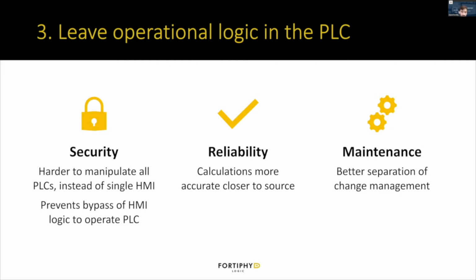For reliability, this helps with calculations being more accurate the closer they are to the source. And for maintenance, it provides a better separation of change management. So keeping the change management and the PLC logic all in the same place instead of being split between the HMI and the PLC.